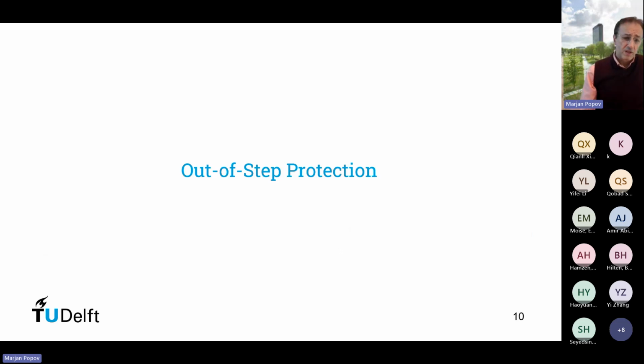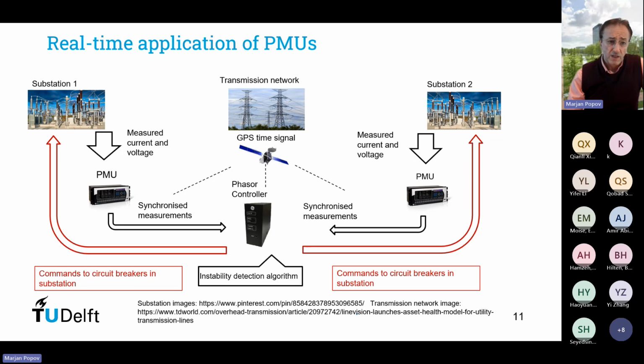I'm going to present one application in this case, out-of-step protection. So out-of-step protection, or loss of synchronism, is a condition when a generator experiences large angular differences from the other generators or the system, or there are large angle differences between neighboring utilities connected by tie lines, for instance. Concerning the application of synchrophasors, I provide here one illustration.